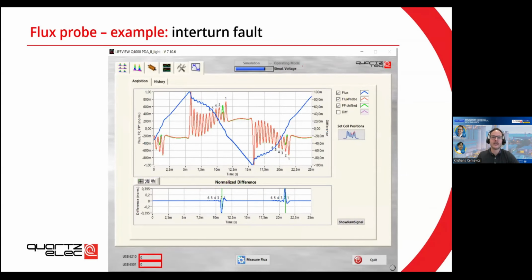So what does a fault actually look like? Here, there's a scenario where coil number 2 has been displaying lower voltage on one of the sides than on the other side. What you can see here is that if we straighten it up and superimpose the two on top of each other, we can actually see the difference. Here we see a difference of around 40% between the two coils, which means, assuming we have 10 turns per coil, that probably 4 of the turns are shorted. So it's a very quick and easy diagnostic, just looking at the differences between the two sides of the generator on the 2 different coils. It's quite fast and quite easy to capture if you have inter-turn faults.